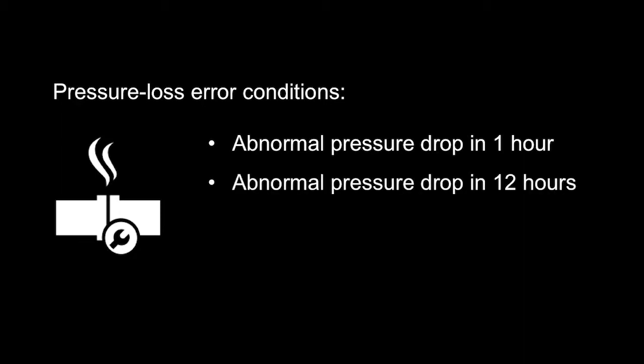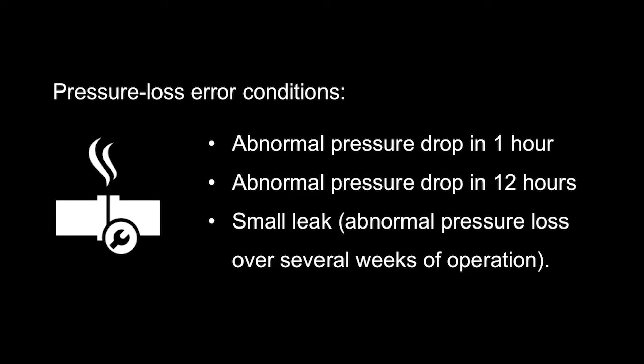Small leaks of calibration gas may be detected by watching for any of the following pressure loss error conditions that are based on readings from the calibration gas pressure sensor: abnormal pressure drop in 1 hour, abnormal pressure drop in 12 hours, small leak, abnormal pressure loss over several weeks of operation. It is recommended to watch for these errors soon after installing or changing the calibration gas cylinder and to contact Morgan Schaefer for assistance if they appear.